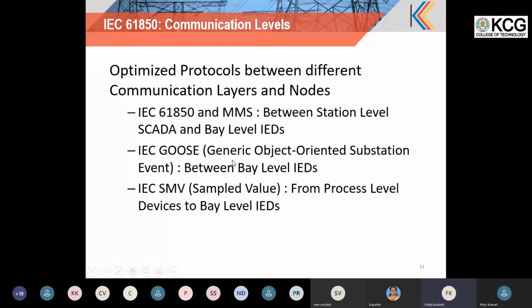Now moving on to process level to IEDs, that is, the raw sample data needs to be sent from process level equipment to the IEDs in the bay. The standard used is sampled values, the methodology for transferring this data from process level equipment to bay level IEDs. So we call it a sample value control block and sample value transfer. These are the methodologies used as per the communication protocol.